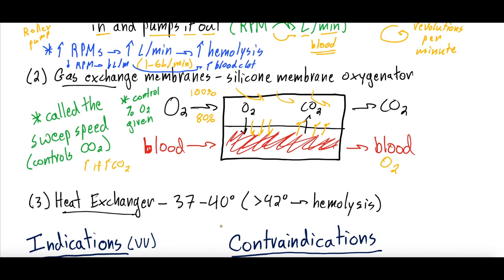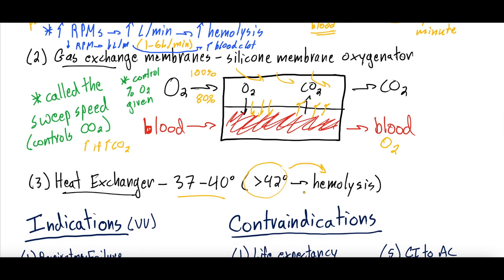The last component is the heat exchanger. Blood leaves the body and you want it to stay warm before returning it. It's typically set to 37 to 40 degrees Celsius depending on the patient's temperature. Of note: temperatures set too high actually cause hemolysis — lysing of red blood cells.